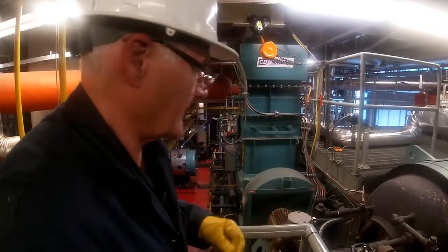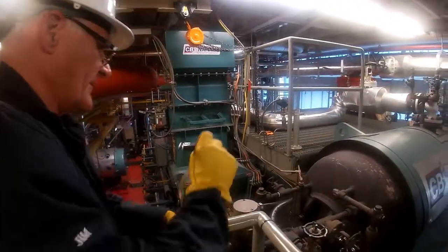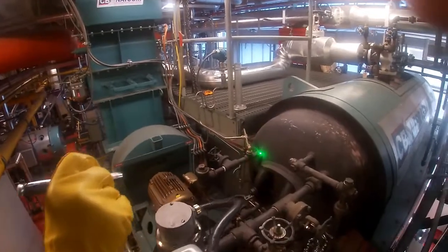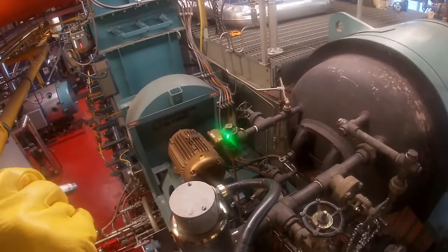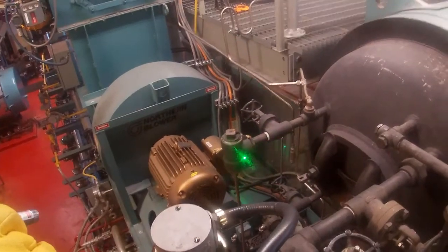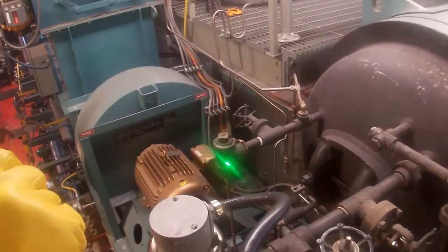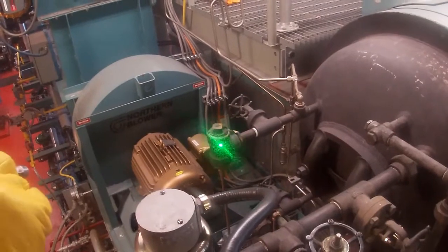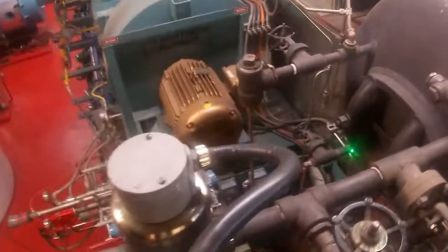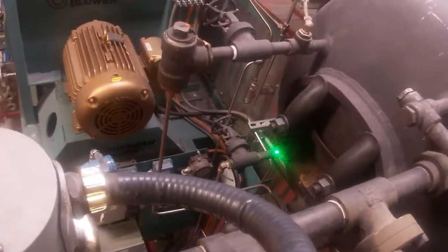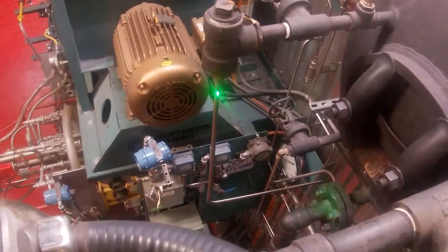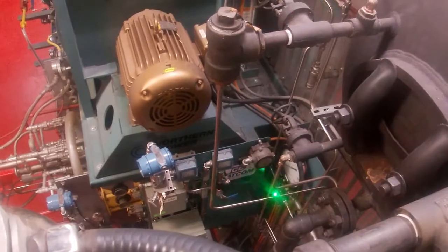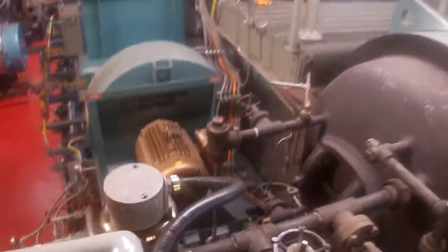While we're here, our water level transmitter, the taps are there. And you can see the tap coming off, and there is my condensing reservoir, which is nothing more than a 2-inch pipe T. And then there is the high pressure tap right down there, and that's going down to the drum level transmitter, as is the compensating leg going down to the drum level transmitter. Okay, we're going to go downstairs.